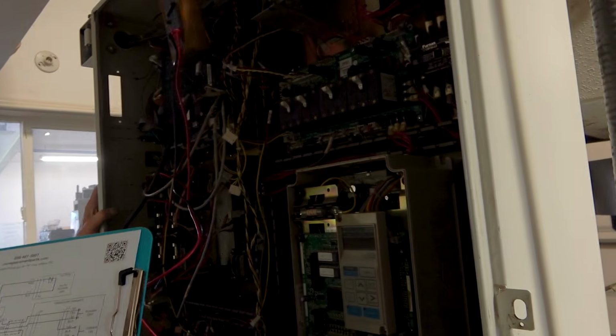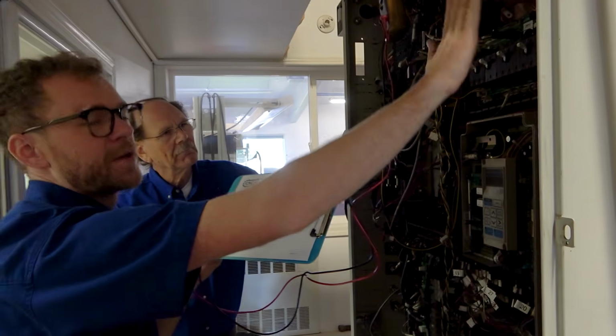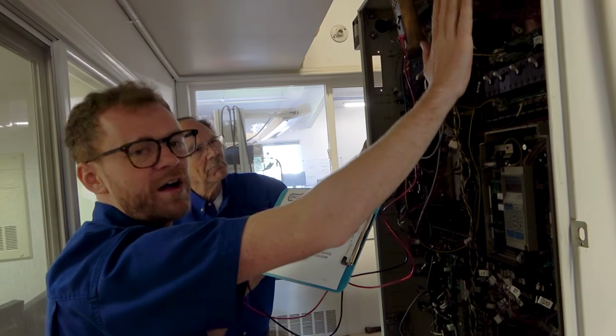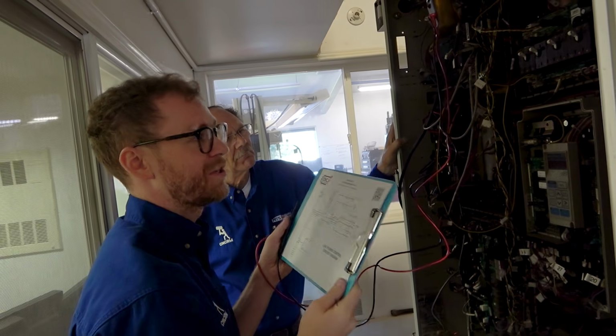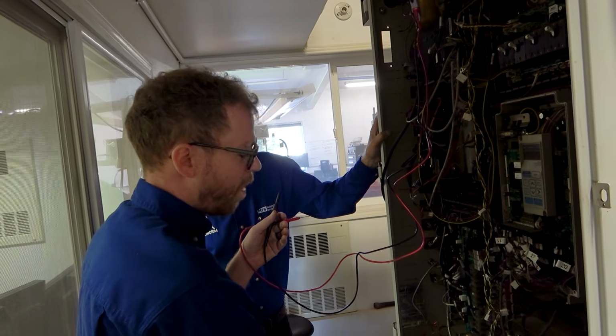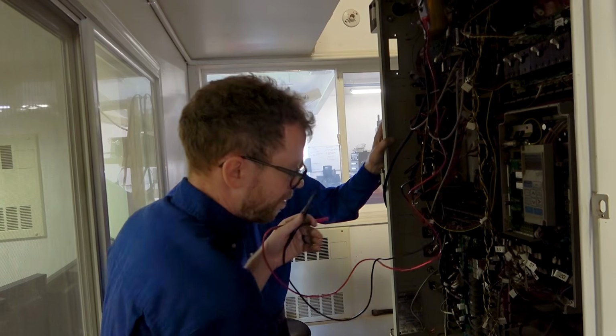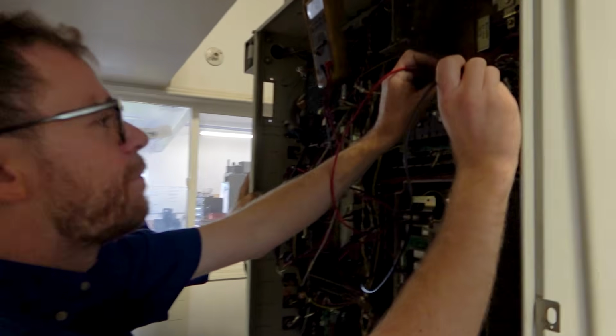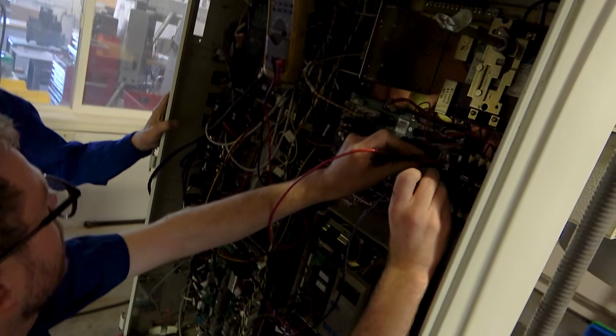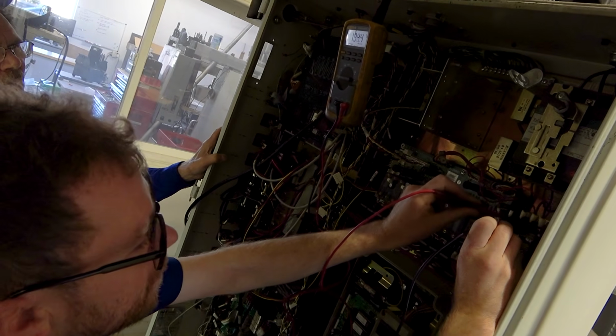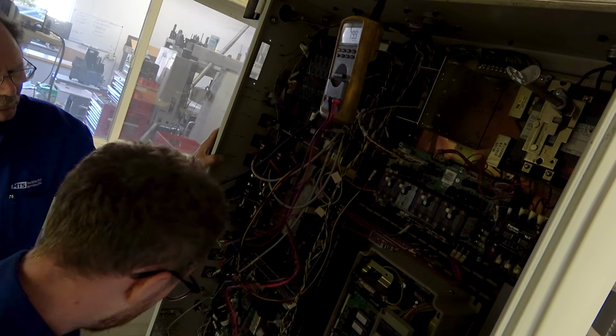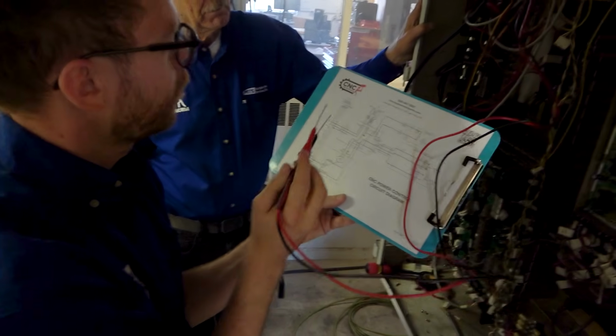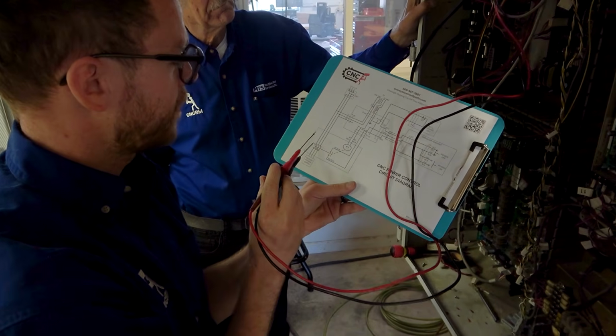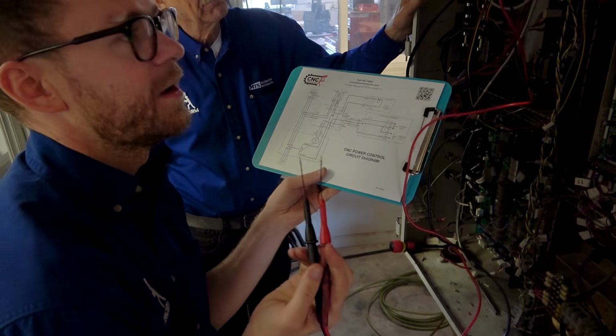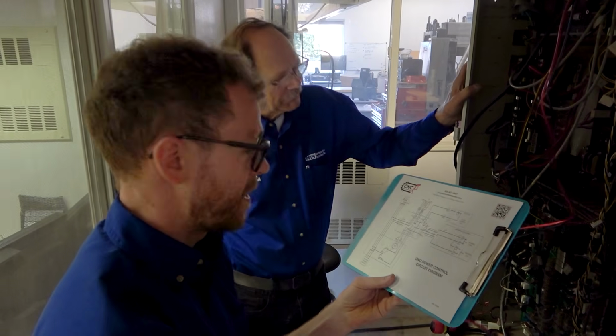Now in newer machines, it can look a little different, and there's a metal bracket or cover in front of it. You're still going to want to check the power, because what if you've got an open wire? So let's check the 3 phases going to the top of the contactor. 250, 248, 250. So looking at this drawing, we know we've got power that's getting to here, to here, and to here. When you push the on button, nothing happens.